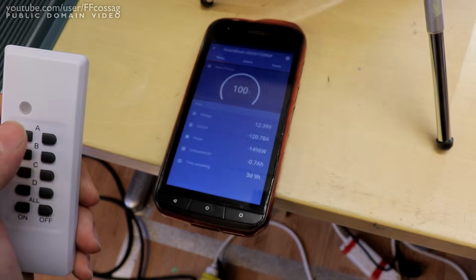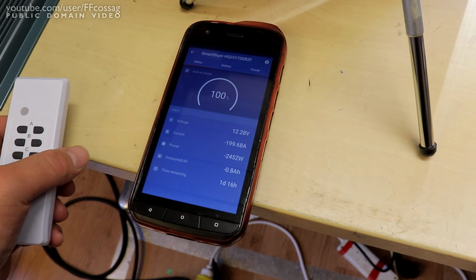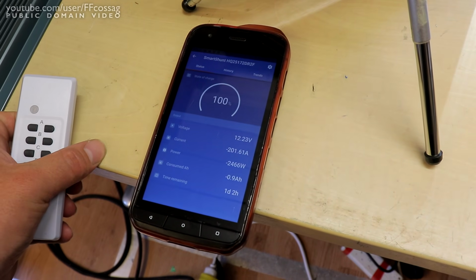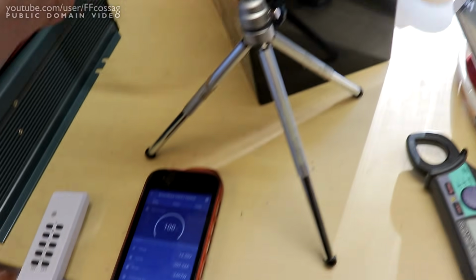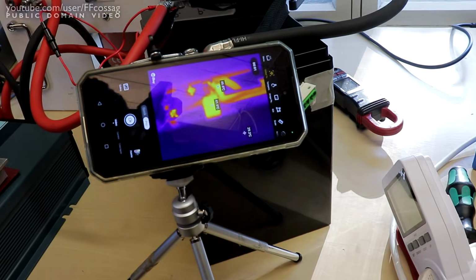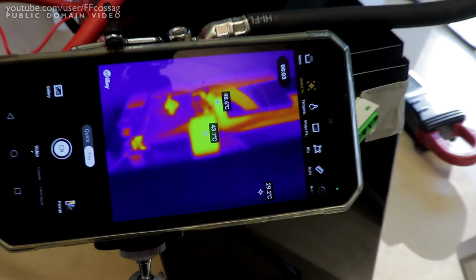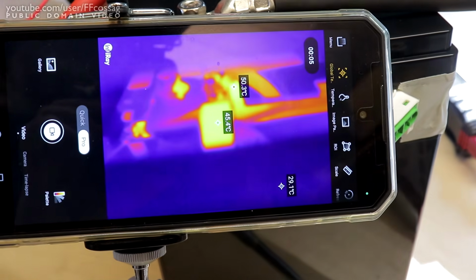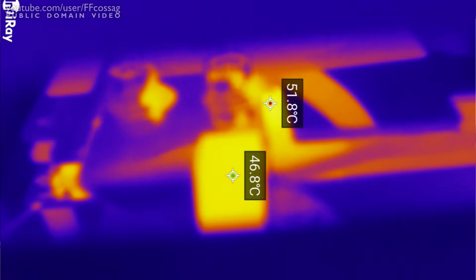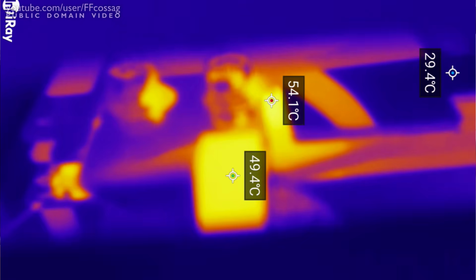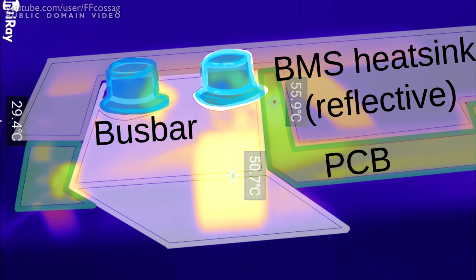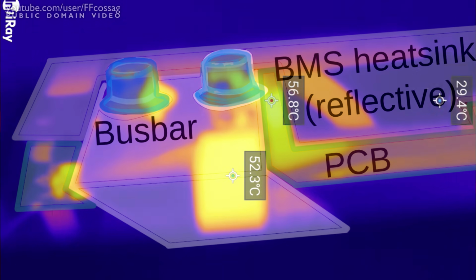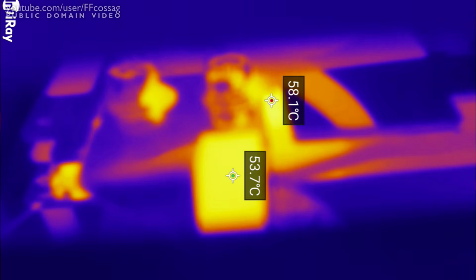We press the button. So that's 200 amps. Leave the battery, and we'll turn on the video recording on there and just see what happens. So this is a severe overload. This battery is rated for 100 amps, so it's overloaded by 2 times. And we can see that the BMS is leading the temperature rise.